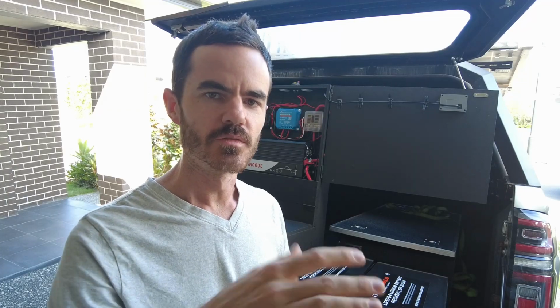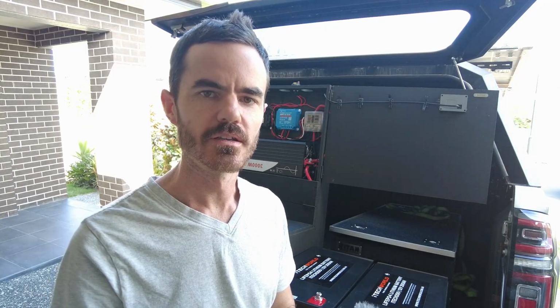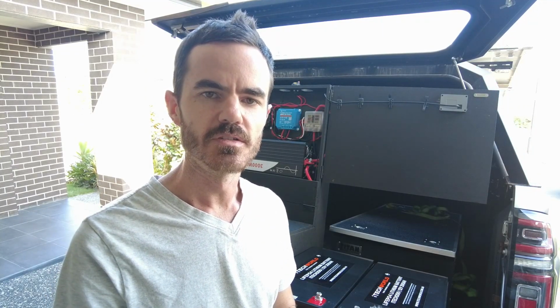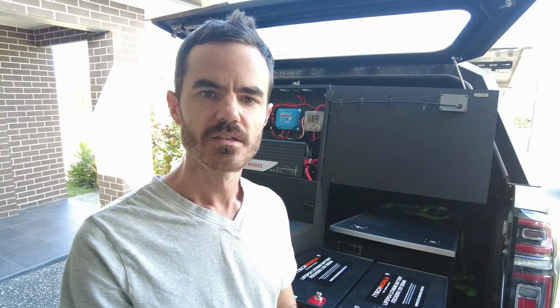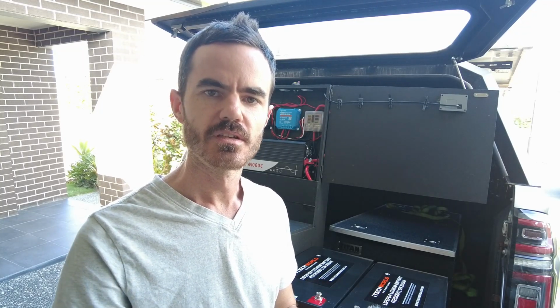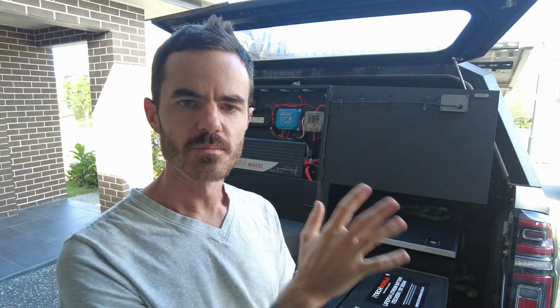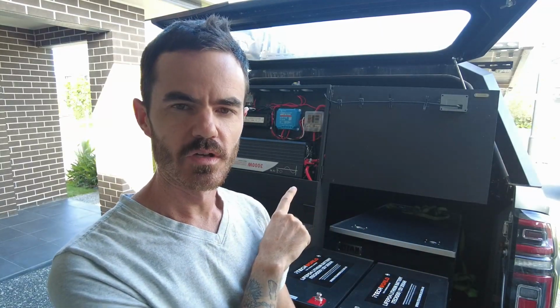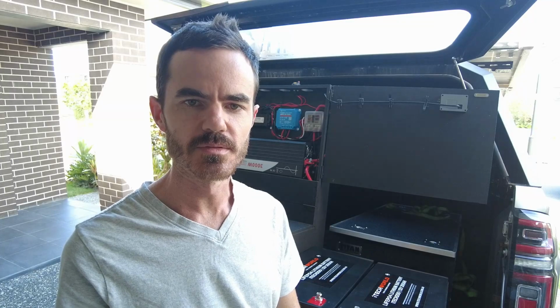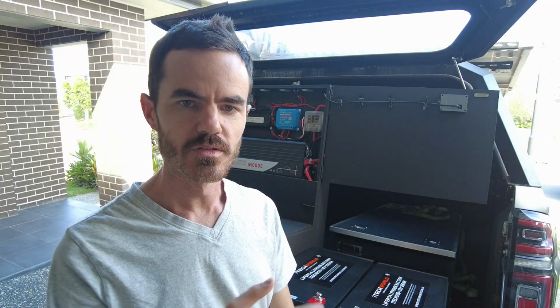And when you jump up to 24 volts, you pretty much halve all your current. So all your amps are halved. That means you can have a lot smaller cables, and you get a lot less voltage drop over distance. It just makes a lot of sense. So I can be running this inverter flat out at 3000 watts and only pull about 125 amps. That's a lot less amps than it would be if it was 12 volt.